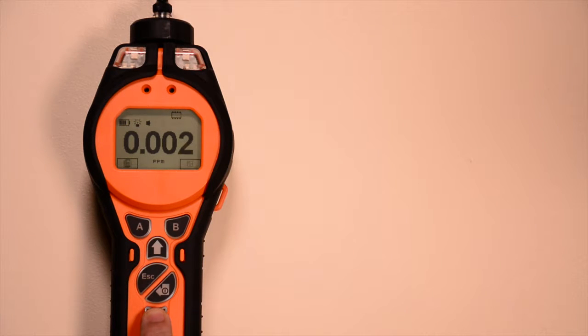Use the up and down keys to find the gas bottle symbol and press the soft key to select it. A single letter will appear. Use the up and down keys to change this letter to T for toluene. Then press Enter. All gases beginning with T are then listed in alphabetical order. Use the up and down keys to scroll through the gas names.